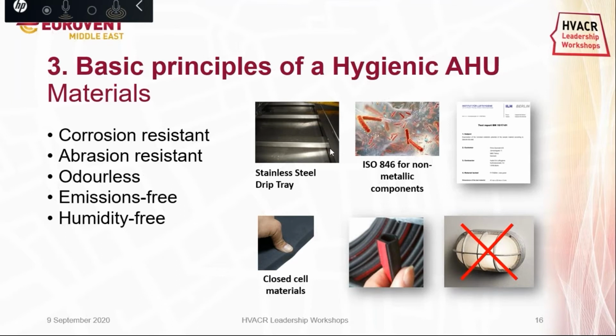Drip trays, drain pan shall be made of stainless steel. Sealings shall have closed cell structure so that it doesn't suck in any humidity. And there are some specific rules in some norms for the door sealings as well. Inspection lighting should be also cleanable. It's mandatory in some sections, but take care that it's cleanable, because as you can see the example on the screen, which is a ship fitting, it's not recommended for hygienic unit because it's not easily cleanable.